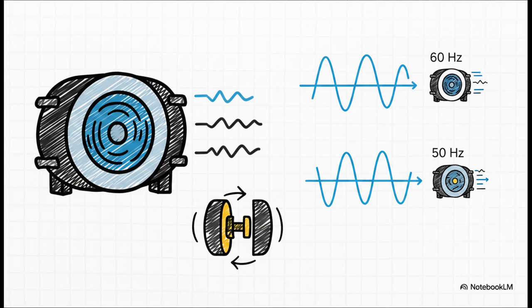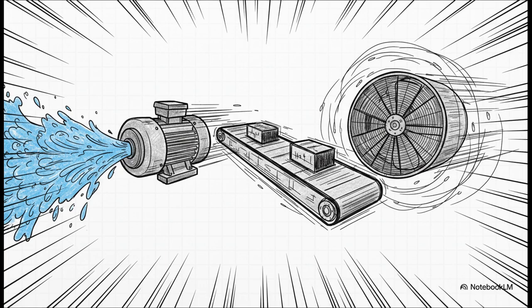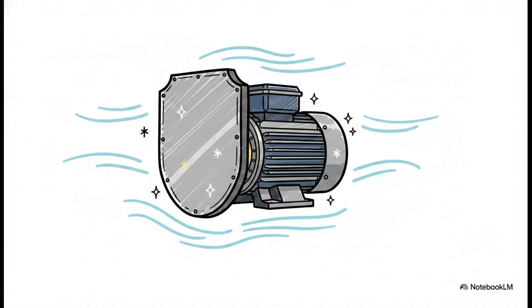3,600 RPM. Think of the 60 hertz grid as a sprinter. By simply operating on a higher frequency, industrial plants get an automatic 20% speed boost from the exact same physical motor footprint. So what does that mean for us? It means higher output from centrifugal pumps, much faster moving factory conveyor belts, and significantly more air being pushed through commercial HVAC cooling fans. But as we all know, speed isn't everything.